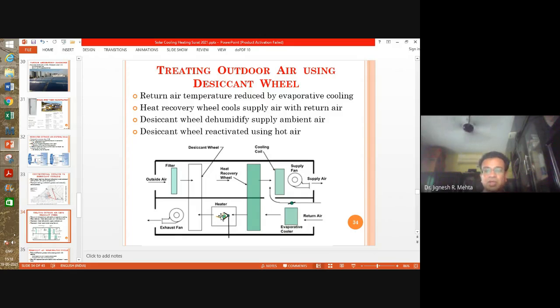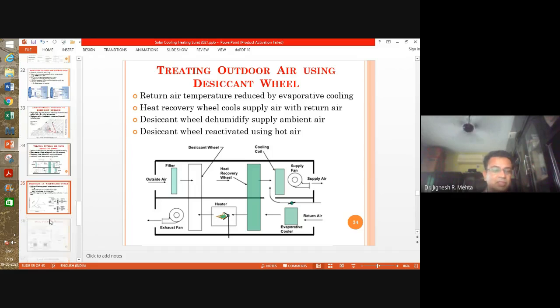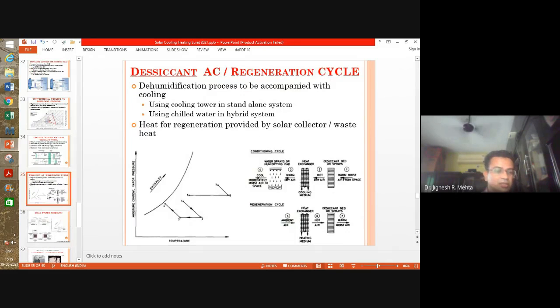Of course, with the new scenario, there is a possibility of cross contamination. This type of system is not recommended for many applications, because the contamination in the room air being exhausted can get transferred to the fresh air going in here. But certainly at least heat transfer is possible with the help of indirect heat exchangers or a heat pipe kind of system. When you are using this desiccant wheel, or it can be a liquid desiccant system also, you can use solar thermal collectors for this application, which provides you the dehumidification.